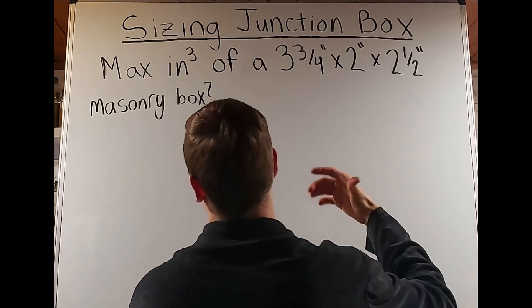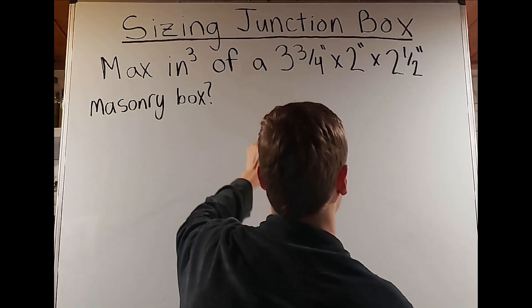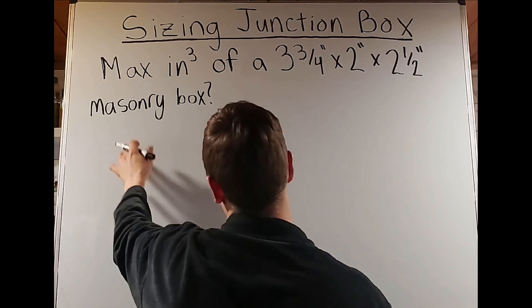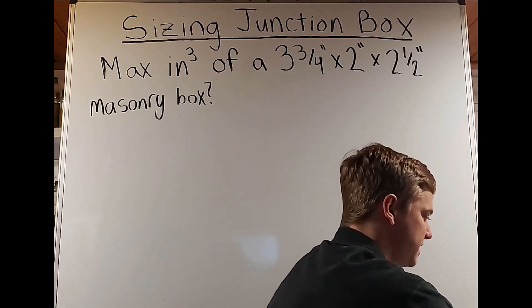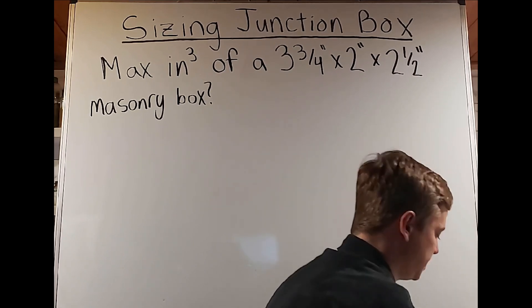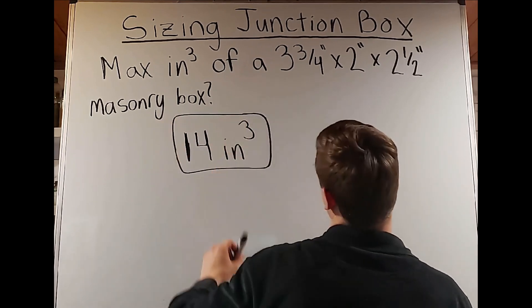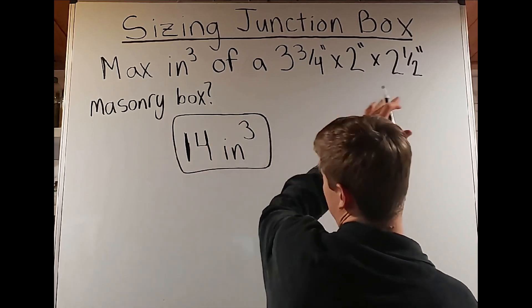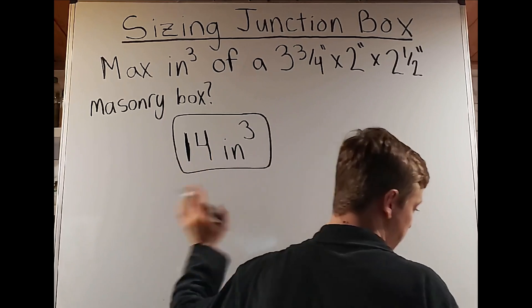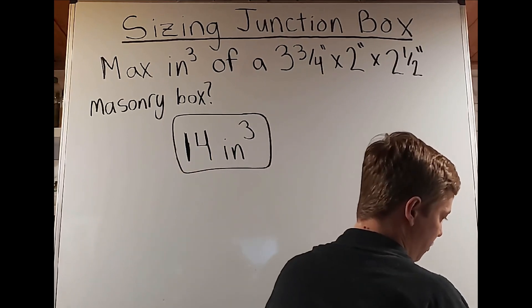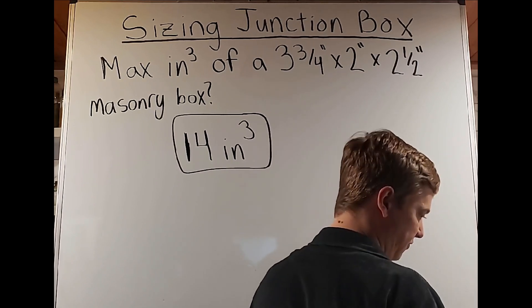Now switching it up: we're looking for the maximum cubic inches of a three-and-three-quarter by two by two-and-a-half inch masonry box. We find that under the masonry box/gang section, and it states a minimum volume of 14 cubic inches. Interestingly, this is actually the maximum amount of space available in this box. So remember — if they ask for the maximum volume of a box, in Table 314.16A you'll be looking under the minimum volume column. Don't let that fool you.